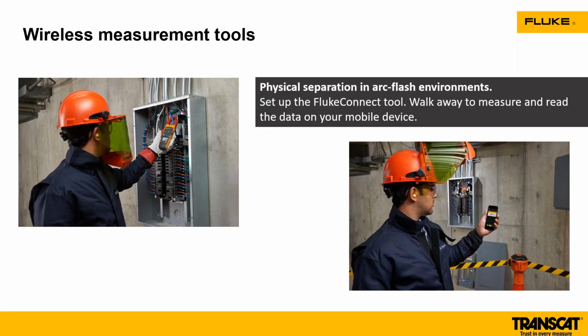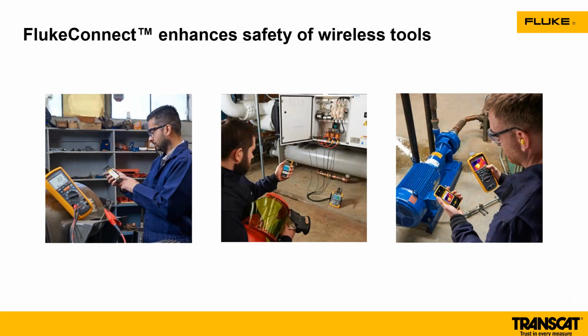Now, when we think about separating ourselves from that boundary, we still need to make measurements. Using some type of wireless tool or a Bluetooth capable tool is a huge win. We can set up the meter, link it into our smart device, and pull ourselves away from that restricted boundary area and make those measurements. We can pull off a little bit of that gear during that process. Really, that's a key win. Again, this whole conversation is how to safely work in those environments. We identified the flashes and what could happen, but making sure that we can stay away from that boundary is where the safety is.